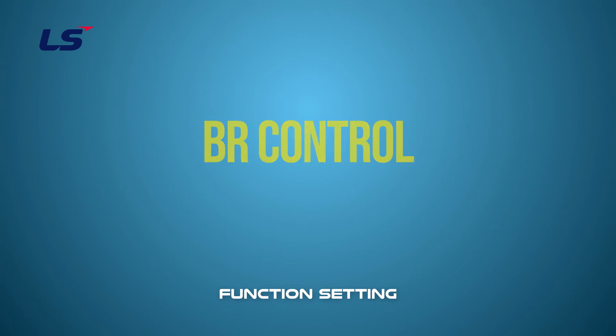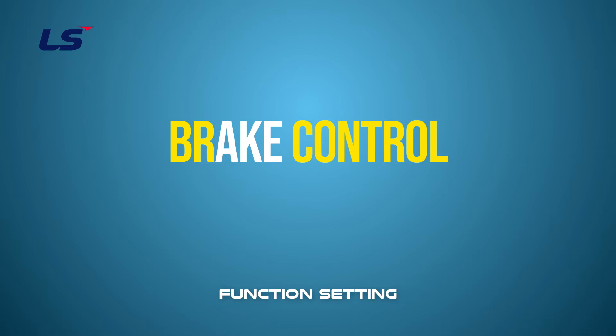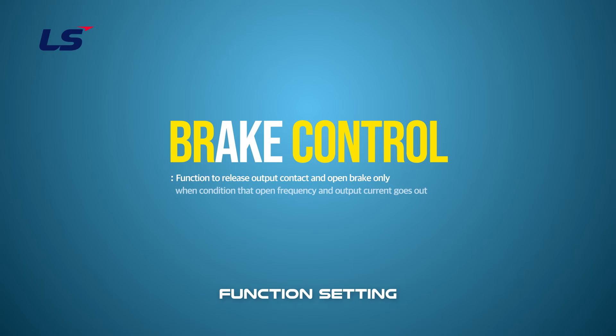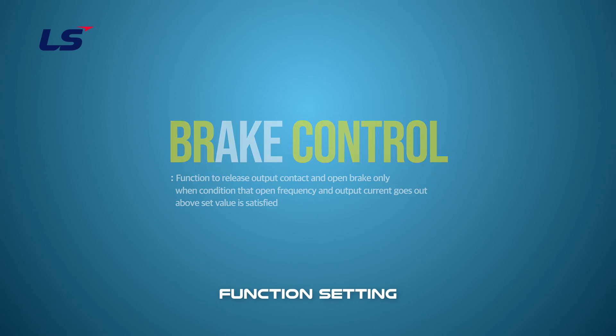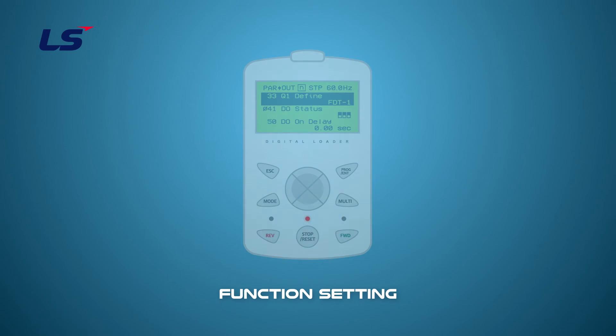Next, we will learn about the BR control functions. If FDT has controlled the brakes according to the output frequency, the BR control function will only release the output and release the brakes if both the output frequency and output current are above the set value.